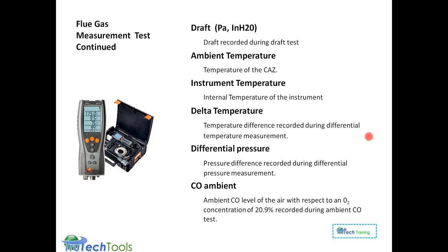Got a quick question here. Is the excess air the same as the O2? Excess air involves what type of fuel you're burning. They do go hand in hand by an equation, but it depends upon the type of fuel. Oxygen is a measured parameter, so it's what the sensor sees. If you have an oxygen level and you look at a certain fuel, you can then say what the excess air is. So they're similar, they're related, but they're related by the type of fuel you're burning. That's why it's important to select the right fuel when the meter asks you to, and to look in the screen and make sure you're measuring with the right fuel. They're not the same thing, but they're related, and they're related through the fuel.